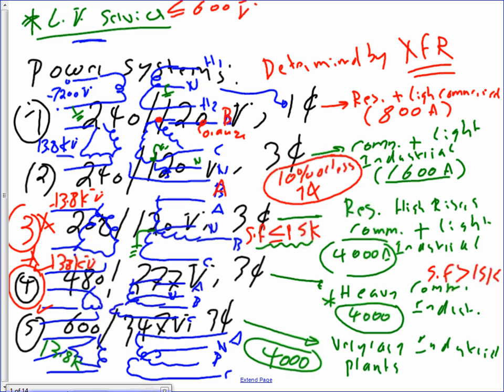And the last system, I haven't seen a lot of it here. The last system, we have 13,800 volt on the primary. On the secondary, 600/347 volt. It's 3-phase, for very large industrial plants. They use a system like this, not commonly used. So these are the 5 most common power systems that you're going to encounter.